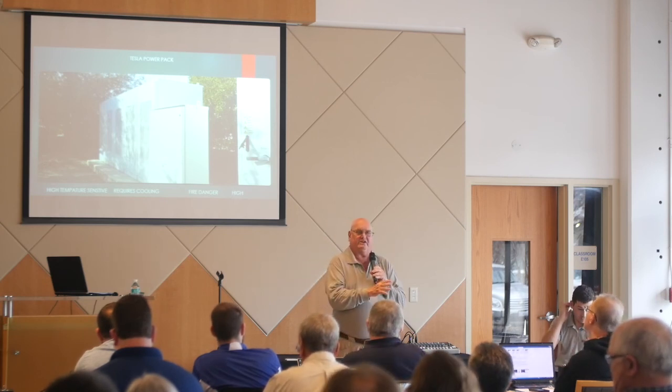So on one end of the spectrum, you have what we call load shedding. On the other end of the spectrum, on a bright sunny day, we can have all of our batteries reaching full state of charge by 10 o'clock in the morning. So what's going to happen? Our voltage is going to begin to rise and our frequency is going to become unstable. And we're going to crash. Well, that's one of the beauties of the hydrogen electrolyzer. It is also a programmable load to us. And it's programmable in 3 steps of 10 kW each.